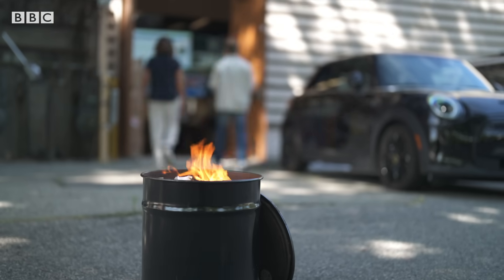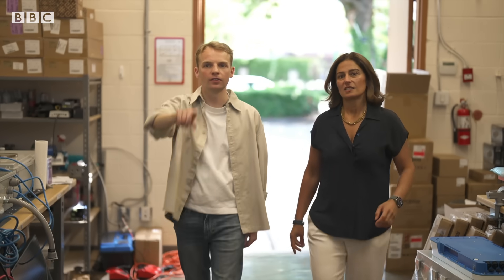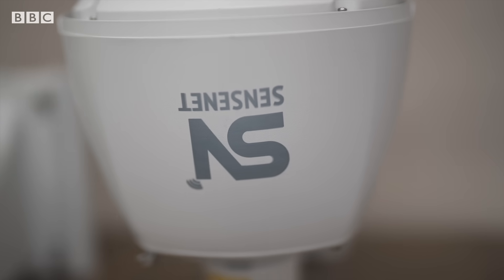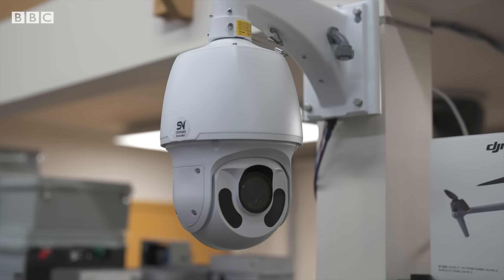We better go inside. This map shows the sensors we've placed outside. We did the fire right in the middle here. They were all green at first, but then two sensors turned red — those are the ones that detected the fire. That was the first one, the second one, the third one. When the alarm goes off, a camera automatically turns to the sensor to check for visible signs of fire and back up what has been detected.